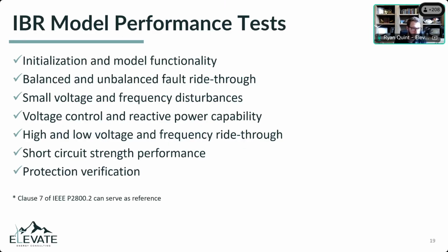Initialization tests, basic model functionality tests, balanced and potentially unbalanced fault ride-through simulations, small voltage and frequency disturbances, looking at the clause 5 and clause 6 type performance characteristics of 2800. You've got the voltage control and reactive power capability - again, clause 5 materials, high and low voltage and frequency ride-through. This is clause 7 checks, short circuit strength checks, protection verification checks, like Alan mentioned.